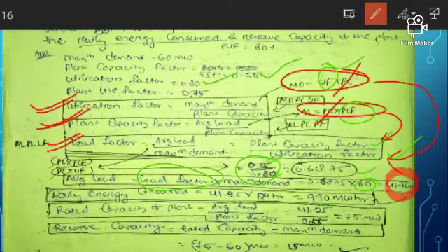So you have got the average load. Now put the average load here in the daily energy consumed, that is equal to 41.25 into 24 hours for one day. After multiplying this term, you will get 990 megawatt hour as your daily energy consumed.